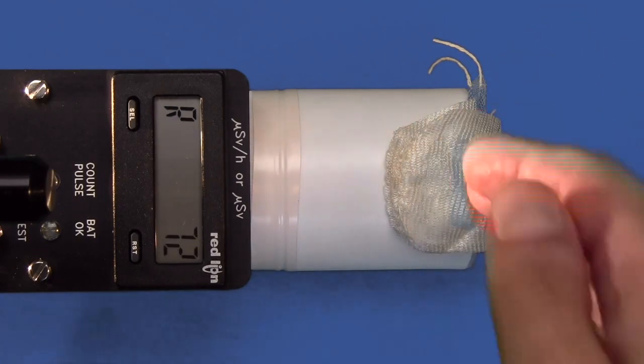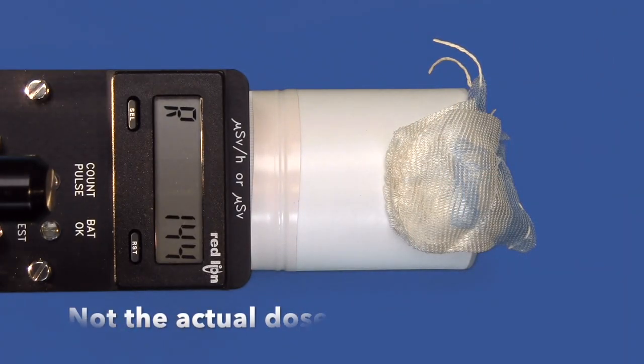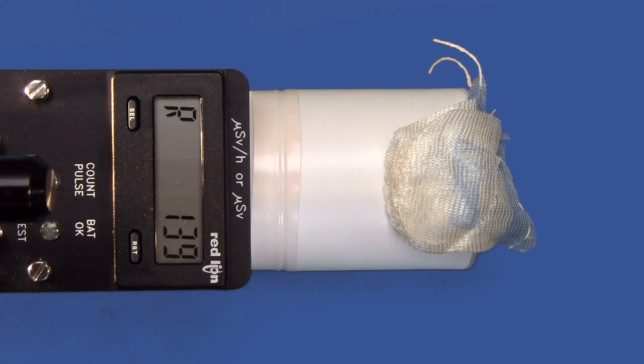This reading represents alpha and beta emission. It does not quantify the actual dose. The range on the survey meter isn't low enough to pick up background gamma radiation, so we know it's mostly alpha and beta.